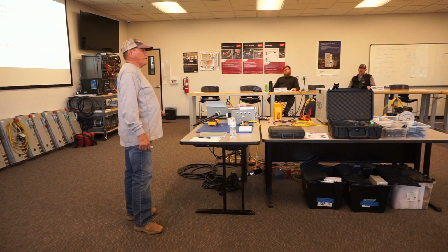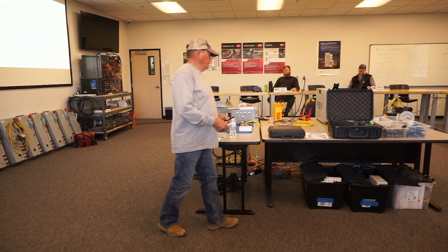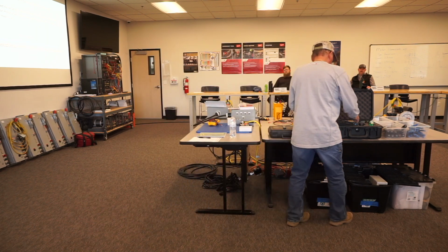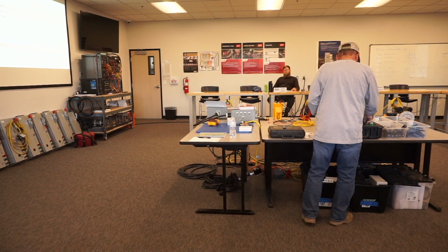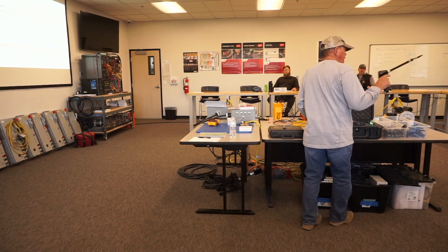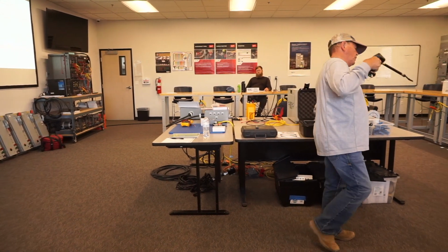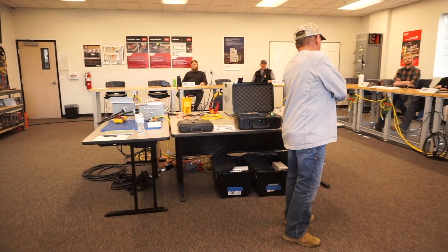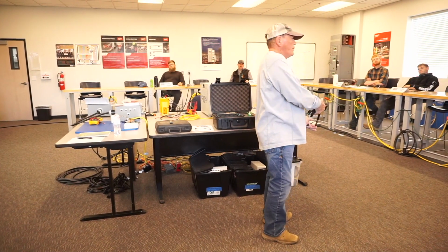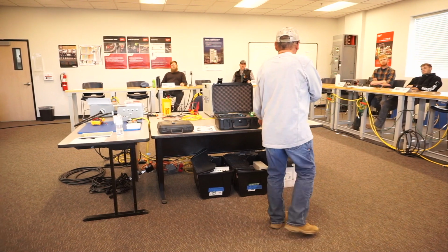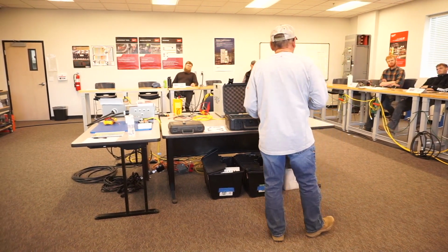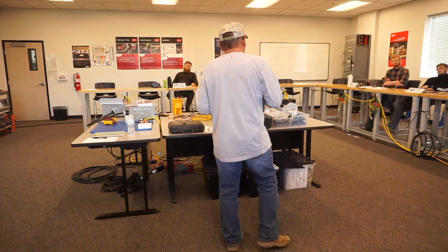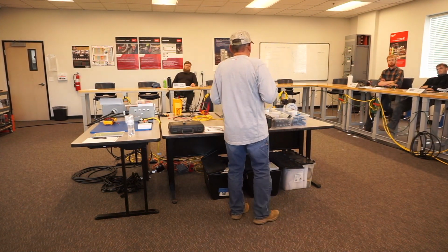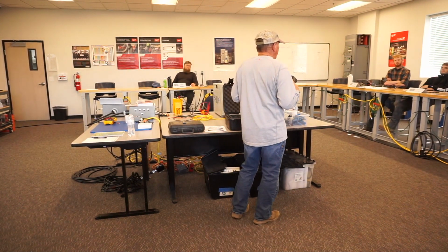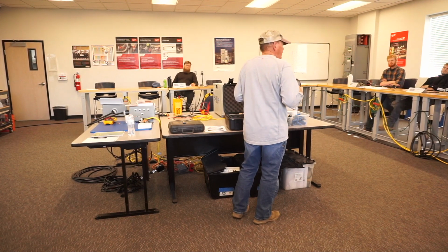So I said, well, let's test it. So I put my meter on. This guy right here, I can put on the shaft of the motor, and I can read the discharge voltage coming off that motor. So it's a very good, unique tool now for me to diagnose motors before they take out the bearings.